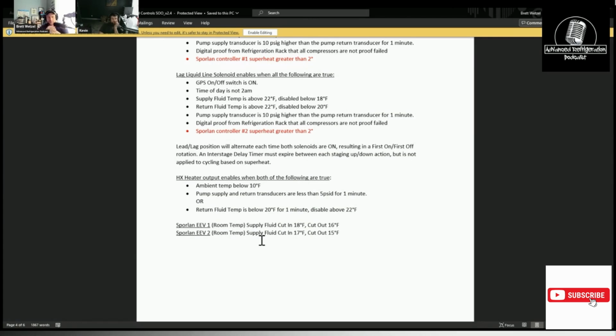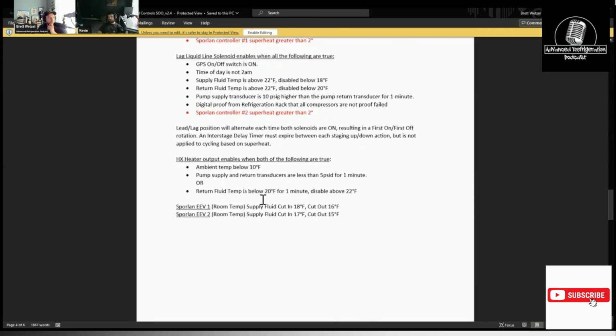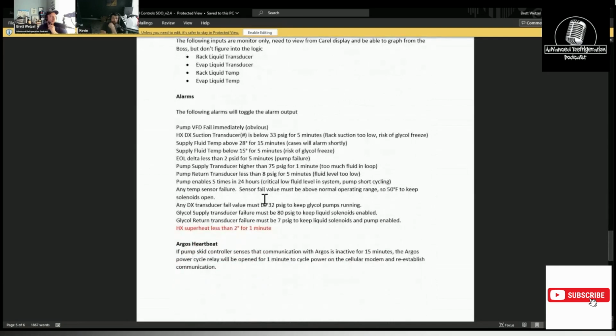Yep. I've even seen that happen on some of the bullseye stuff where you have the remote header and sometimes they don't get enough subcooling because they're having to run up and over, so they put those in there to give you a little bit more subcooling and protect from lower superheat coming back. So you'll have that in there. They do work, but the problem is you're robbing Peter to pay Paul, but you have a lot to rob from Peter because your superheat's so low. But they're not reliable. If they were brass, it'd be awesome. If they're just all one solid piece of brass. Yeah, because there's no way, I don't care how good you insulate that, you're never going to keep it from sweating.